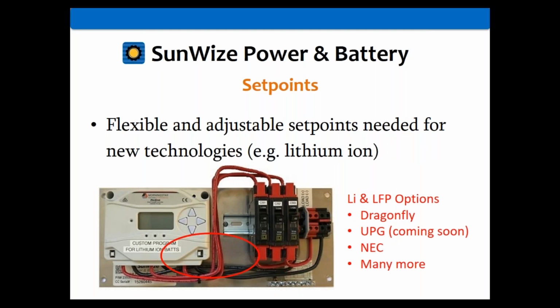This is becoming incredibly important with new technologies like lithium ion as well. Here's an example we did for a customer—we even put a special note on it saying the unit had been custom programmed for lithium ion batteries, since we didn't want someone to use those settings on a lead acid battery, which would damage it.